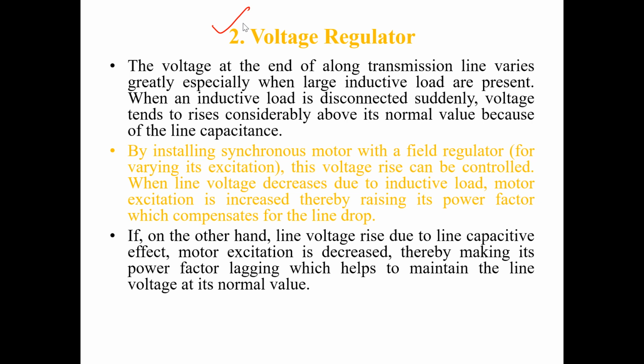And this application, this type of voltage regulator, the synchronous motor, is used in long transmission lines. Because in a long transmission line, due to voltage drop, the voltage across the last consumer is very low as compared to the first consumer. So to increase the voltage level of that last consumer up to a minimum or optimum value, we need some voltage improvement techniques.